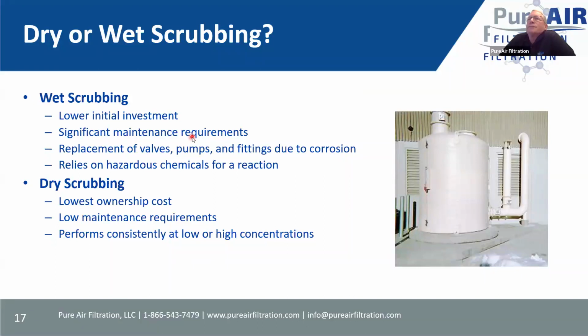Wet scrubbing: lower initial investment, significant maintenance requirements. Again, we'll talk about that. But anytime that you're dealing with caustic solutions, you're going to have issues with the valves and the pumps and the lines if they're not properly maintained. And with this piece of equipment, it's very important that it works when it is called on. And just like I was talking about, some things that come with the wet scrubber are replacements of valves, pumps, and fittings due to corrosion. It relies again on a hazardous chemical for the reaction.